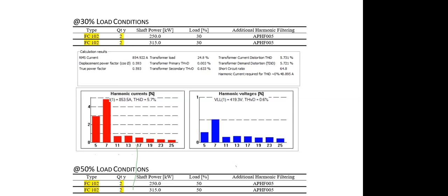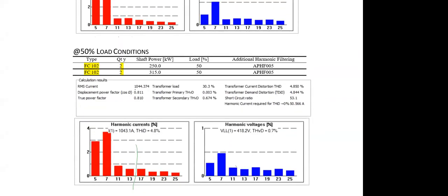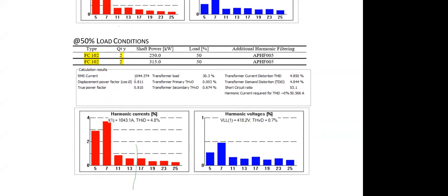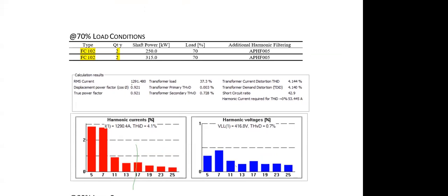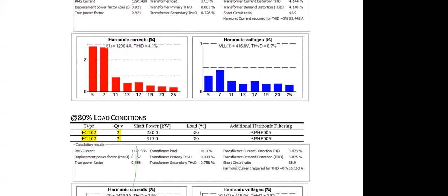Shaft power, that is kW, is 250, another one where the kW is 315, and load is at 30%. As you see, the total harmonic distortion at 30% is 5.7% for the current, and for the voltage it is 0.6. Now you see the difference between current and voltage. That's why again I'm saying the total harmonic distortion has to be calculated. Now in case of 50% load condition, the current harmonic is always high compared to voltage. And this is 70% load, and in a different load condition it is given differently.